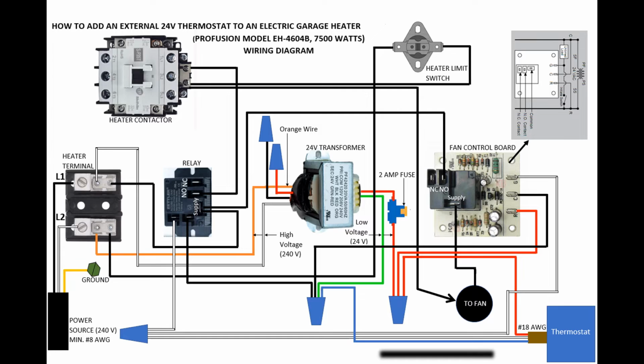Now the delay on break works like this: when you turn the thermostat off, the contactor will open and the heating elements will shut down, but the fan blower control unit will keep the fan running for 60 seconds to cool the heating elements and get all the heat out of the coils.